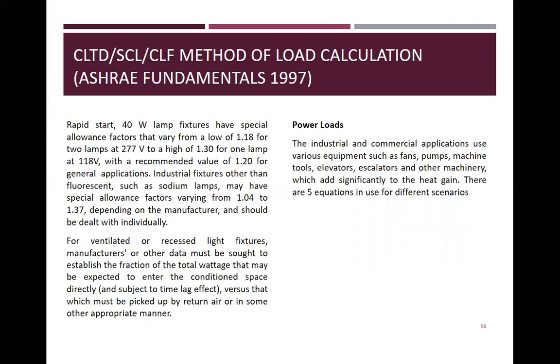For ventilated or recessed light fixtures, manufacturers' or other data must be sought to establish the fraction of the total wattage that may be expected to enter the conditioned space directly and be subject to time lag effect, versus that which must be picked up by return air or in some other appropriate manner.